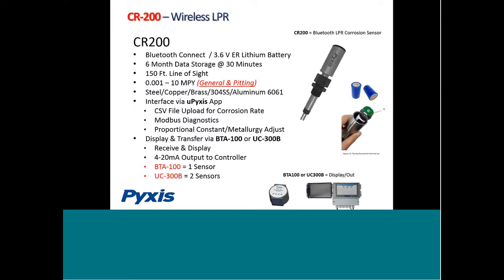So we'll talk a little bit about the CR200, which is the wireless version. Again, we provide a battery. It's a 3.6-volt lithium battery, and that battery will provide you approximately 6 to 9 months of operation with 6 months of data storage in the actual probe itself at a recording frequency of once every 30 minutes. So when you configure the probe itself, you'll have the flexibility to configure it to record continuous, 1 minute, 3 minutes, 10 minutes, 30 minutes, or 1 hour. If you program it to 1 hour, that device will store 6 months of data in the probe itself. Batteries will last you about 9 months.